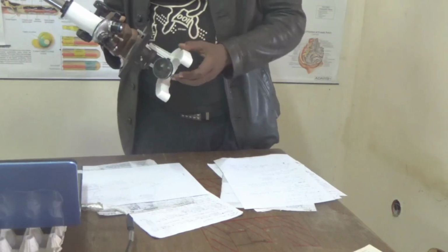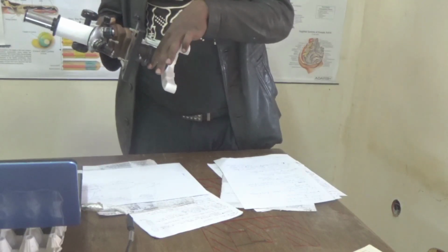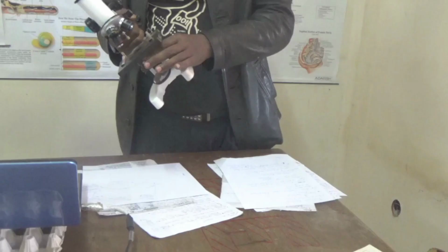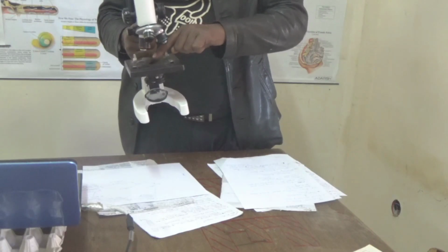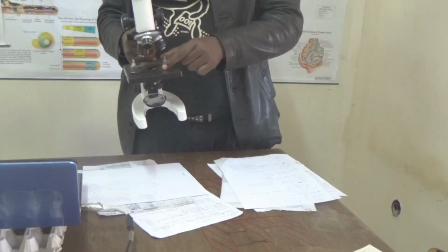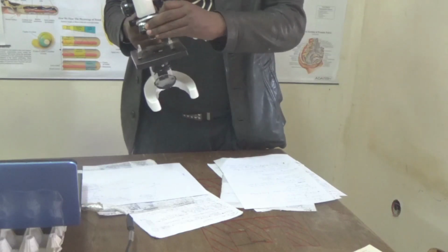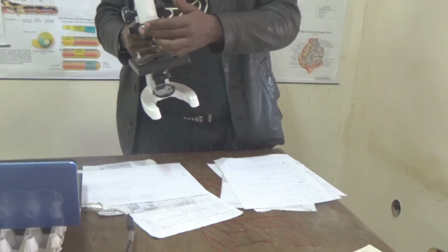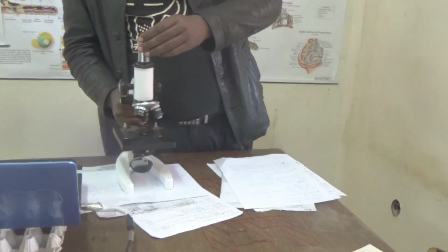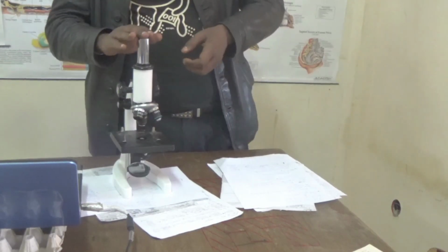The light source is reflected into the iris diaphragm, and the iris diaphragm controls the amount of light. This light is formed by a condenser lens into a converging point where we have the object, and the light passes through the object and enters another lens, of a different power, low, medium or high. Through the two lenses, the image is magnified and seen through the naked eye.